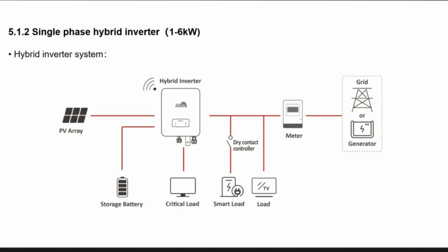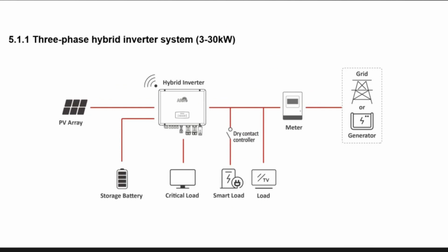And also, the generator could be connected with the ATS kit. This generator could work as a backup or peak shaving when there is no grid, and during the night, no PV. And also, if the battery is low, the generator could provide the energy to the load and at the same time charge the battery. Or if the grid is on, the generator could act as peak shaving during peak hour price rating. This condition is not the normal one.